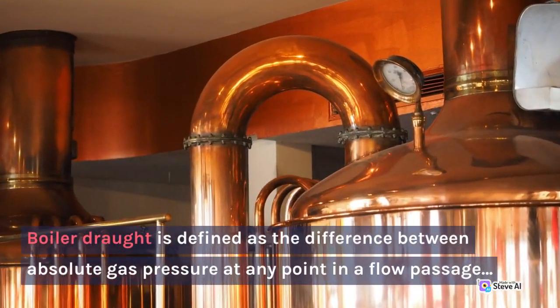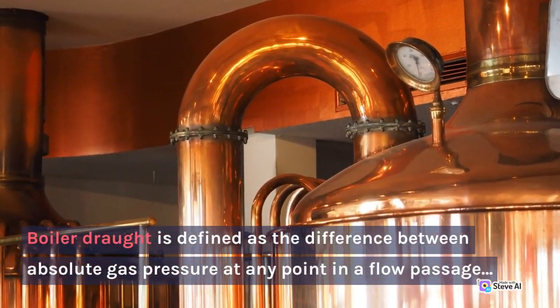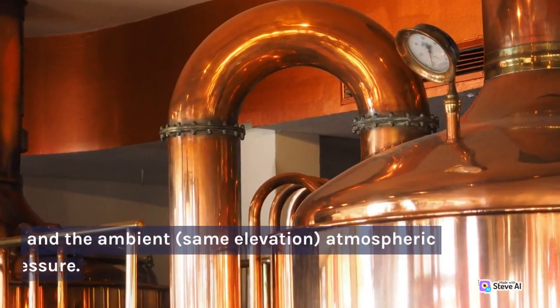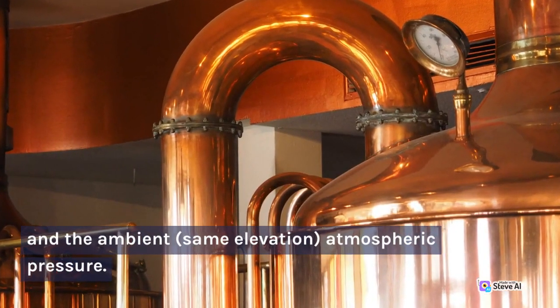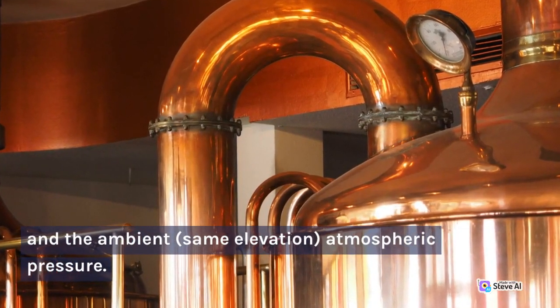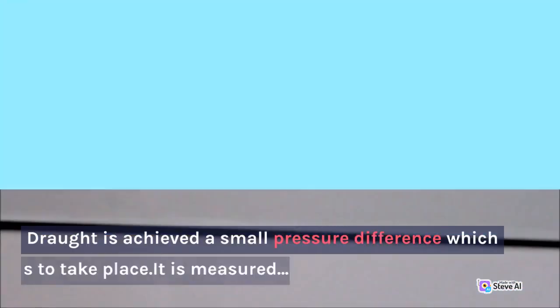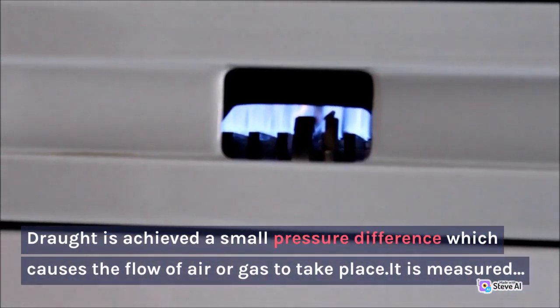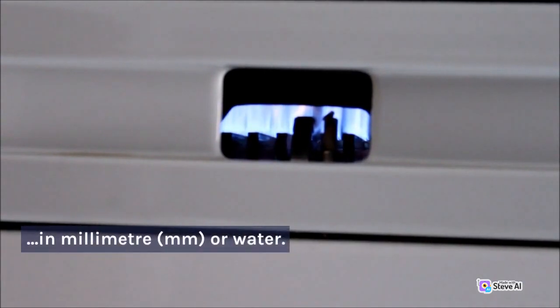Boiler draft is defined as the difference between absolute gas pressure at any point in a flow passage and the ambient, same elevation, atmospheric pressure. Draft is achieved by a small pressure difference which causes the flow of air or gas to take place. It is measured in millimeters of water.